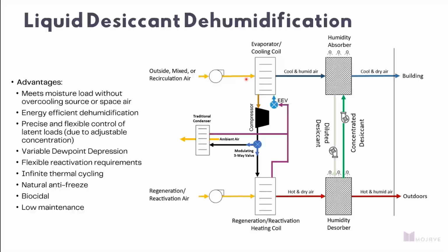Coming off this coil saturated, anywhere between 60 degrees and 75 degrees Fahrenheit dry bulb, 100% RH. And then you pass that cool, saturated air through our humidity absorber. I'll show what that looks like on the next screen here. And basically what's happening is as you pass through this humidity absorber, that high vapor pressure saturated air is interfacing with the low vapor pressure of our liquid desiccant, and that passive dehumidification process begins. And what's happening here is you're condensing moisture out of the air, going from a vapor state to a liquid state. It's a latent heat of condensation.